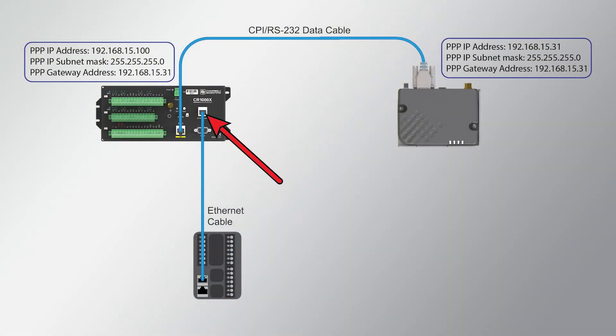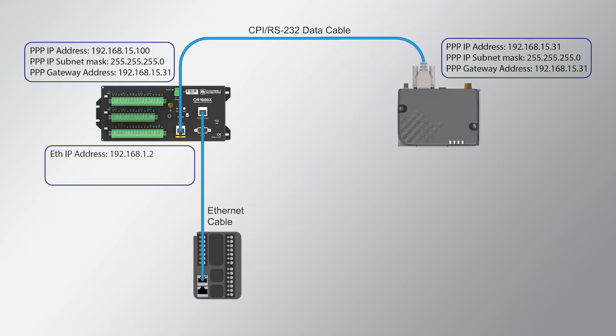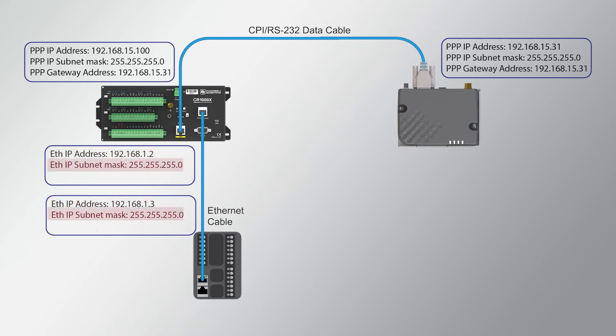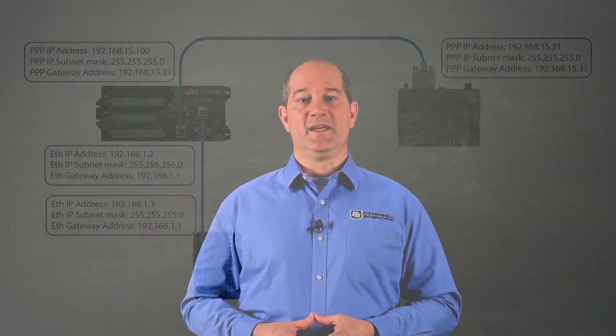Next, a different IP stack is configured on the CR1000X's Ethernet interface. The CR1000X is connected via Ethernet to a generic Modbus Programmable Logic Controller, or PLC. The CR1000X is given an address of 192.168.1.2, while the PLC is given 192.168.1.3. The subnet mask remains 255.255.255.0 for both components, and both are given a gateway address of 192.168.1.1. In this instance, the gateway address could be anything, as this network will not be communicating with any hosts outside the local network.